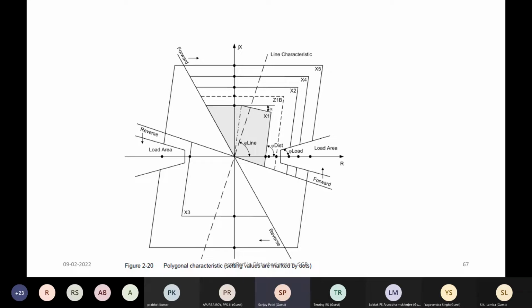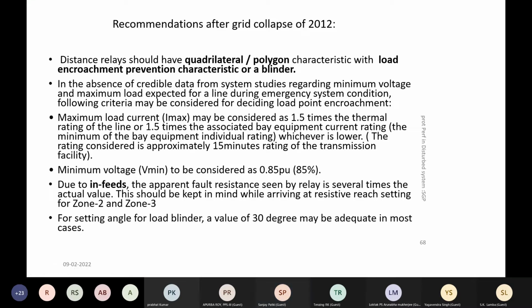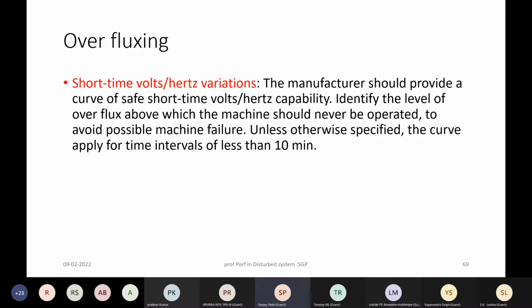So basically the thermal rating of the line into 150%, accompanied by low voltage conditions to the extent of 85%. So that is the criterion which has been recommended for which the tripping should not occur: 150% overload of the conductor accompanied by 85% undervoltage condition. For that, the tripping has to be prevented. So that is basically the recommendation which is given in this slide.